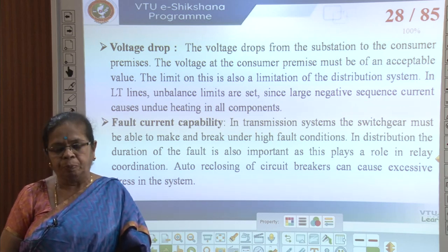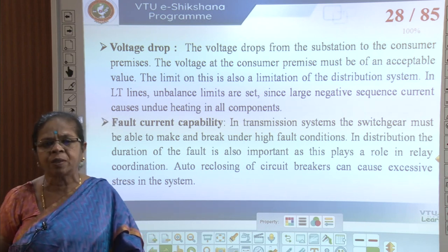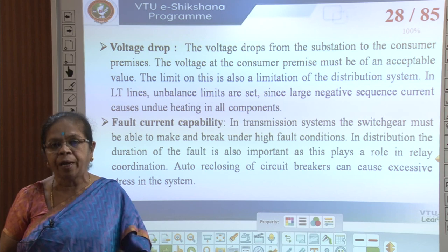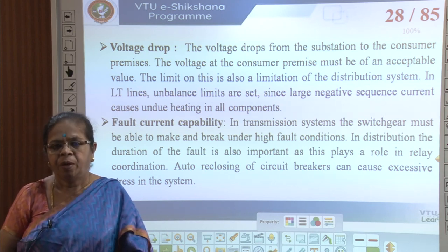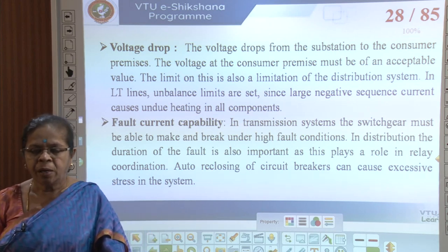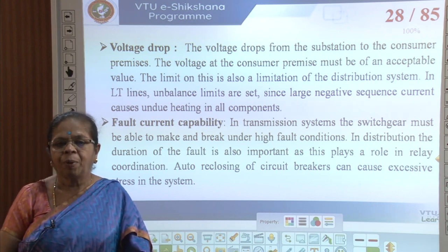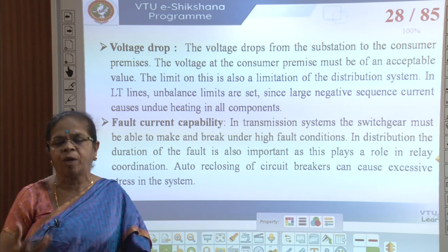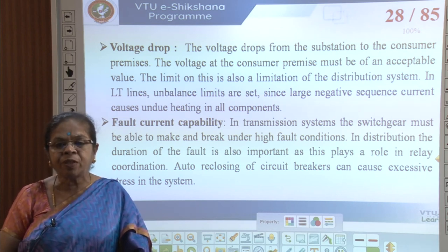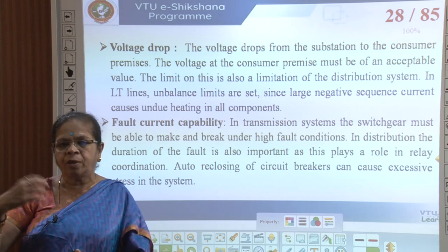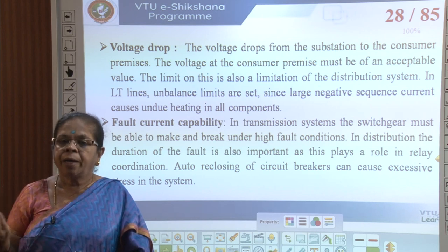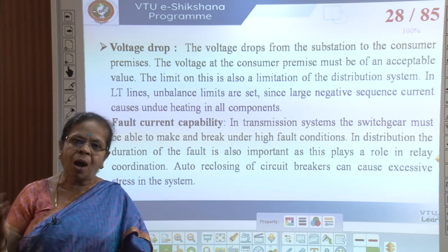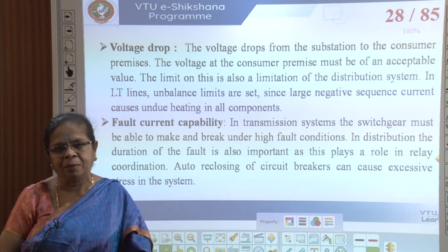Next we consider voltage drop. The voltage drops from the substation to the consumer premises — there is always some drop under normal operating conditions between the sending end and receiving end, and this has to be within a limit. We also limit unbalance in the lines because too much unbalance causes negative sequence current — a component of phase current with opposing phase sequence to the normal current. If the normal sequence is R-Y-B, negative sequence currents have R-B-Y, and these cause heavy losses in equipment.